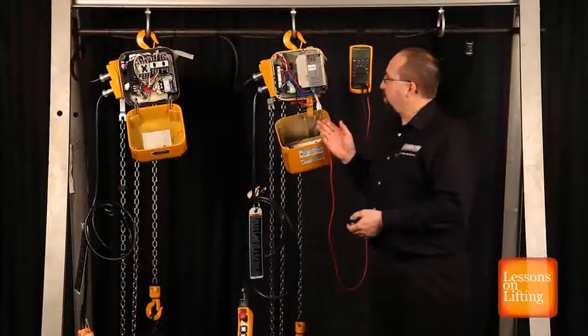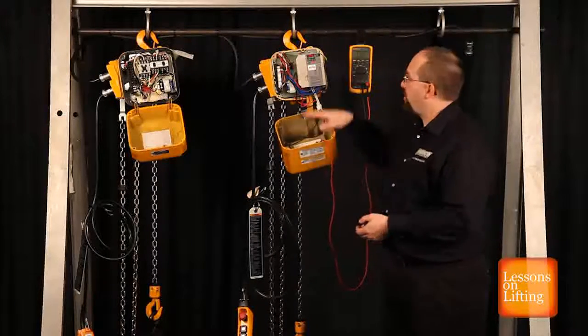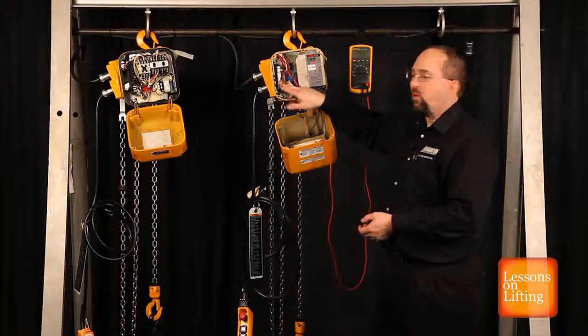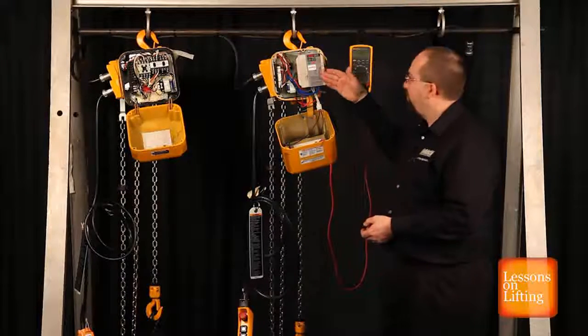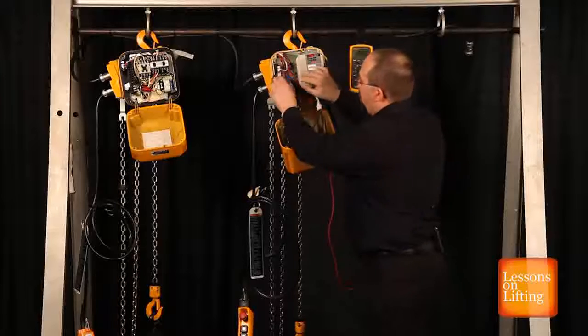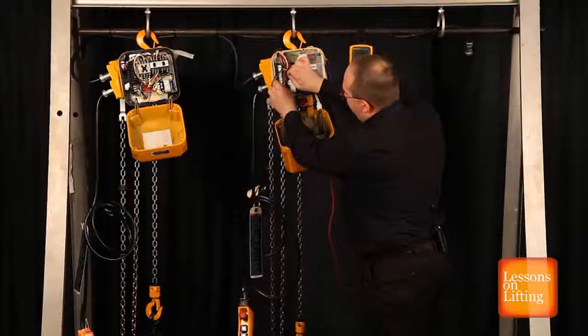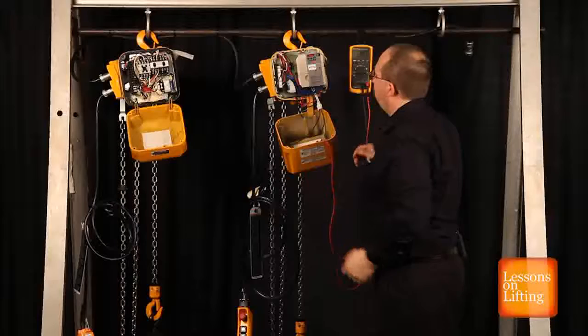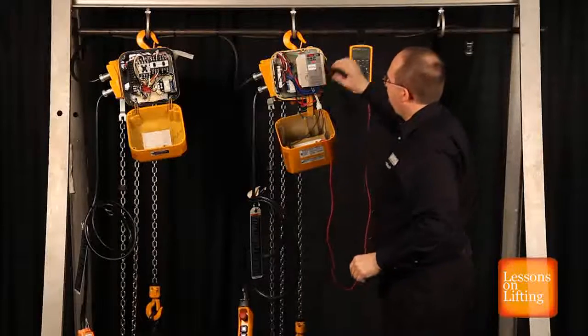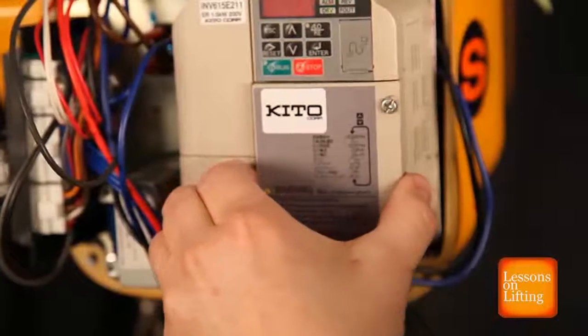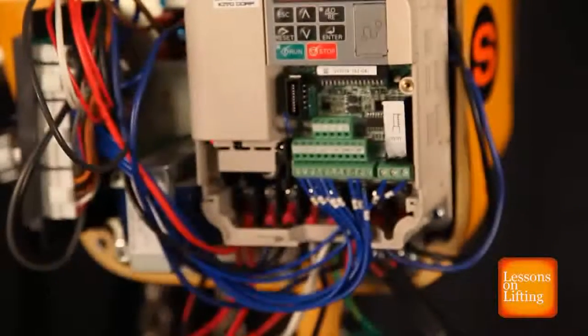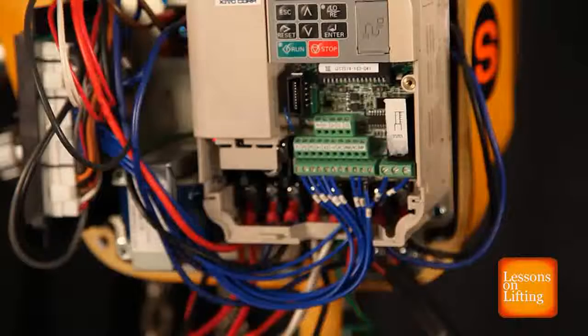If the relay does work, we're going to move to CN12, which is the output from the interface board to the VFD. So, real simple, we just want to make sure that the connector is fully seated and engaged with the interface board. This one is. We're going to say that looks good. So the next step is to go to the VFD itself. Take that cover off.